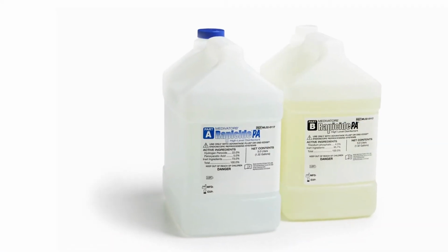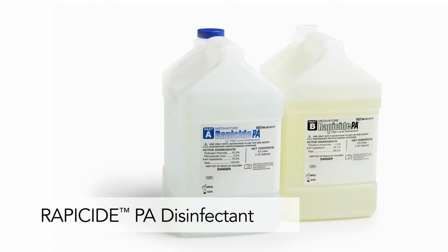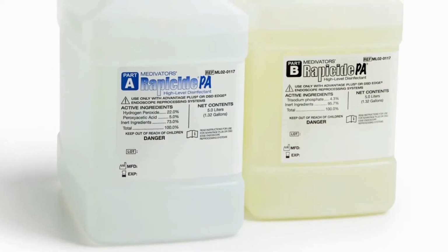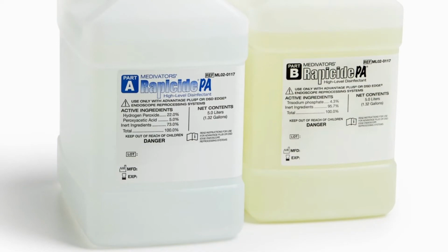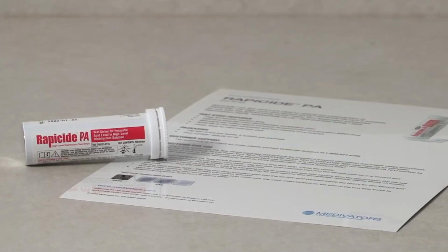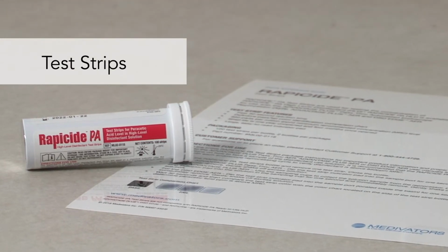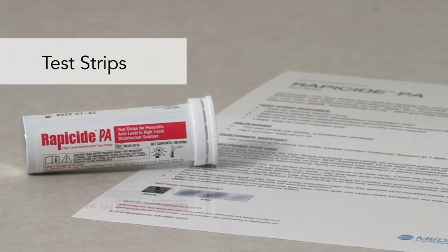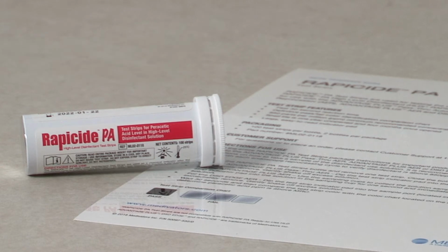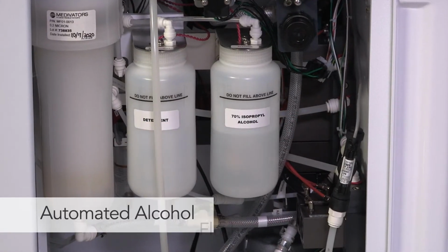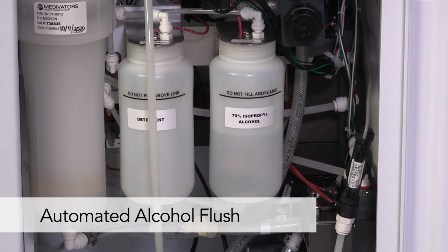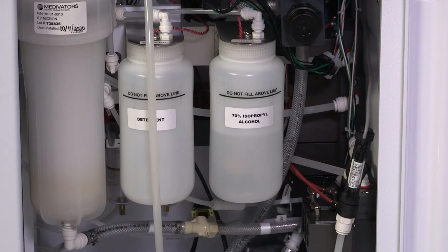Single-use high-level disinfectant, Rapicide PA Disinfectant, means each reprocessing cycle uses a fresh batch of disinfectant solution. We'll learn more about Rapicide PA Disinfectant in the chemistry segment of the video. Rapid and easy-to-use Rapicide PA test strips are used to measure the minimum recommended concentration, or MRC, of Rapicide PA Disinfectant with a definitive pass-fail color chart. An automated alcohol flush facilitates water displacement from the channels, which aids in reducing residual moisture, preventing bacterial growth.